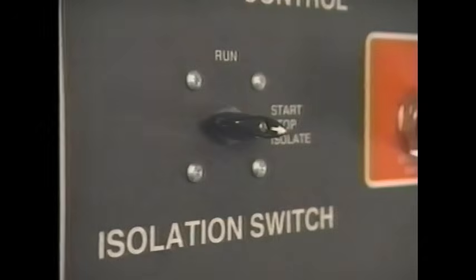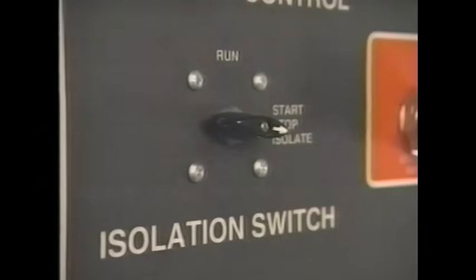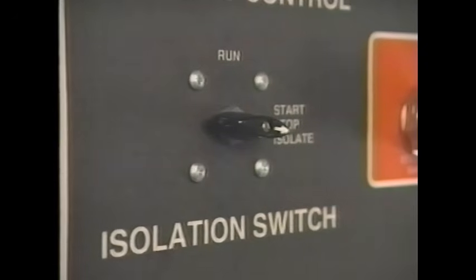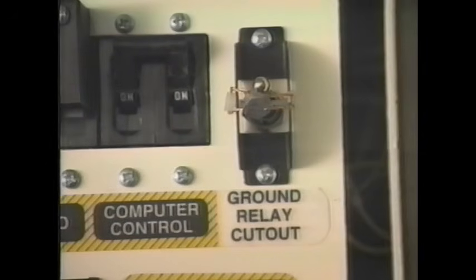Next, check the isolation switch on the engine control panel. Make sure it's in the start, stop, isolate position. Then, in the switch and circuit breaker cabinet, close the battery knife switch. Make sure the ground relay cutout switch is closed and that the auxiliary generator circuit breaker is on.